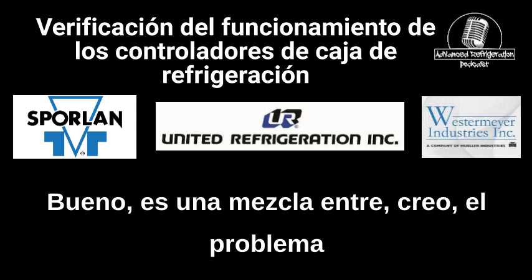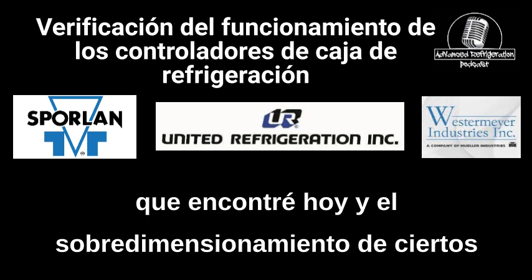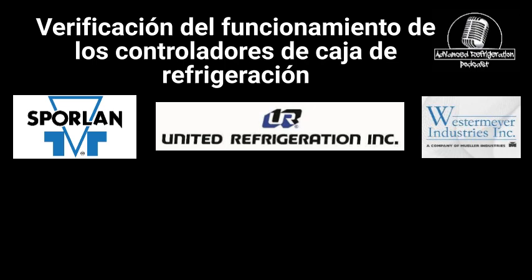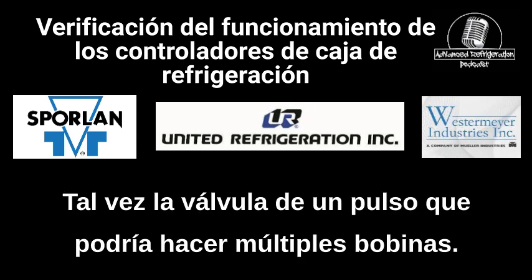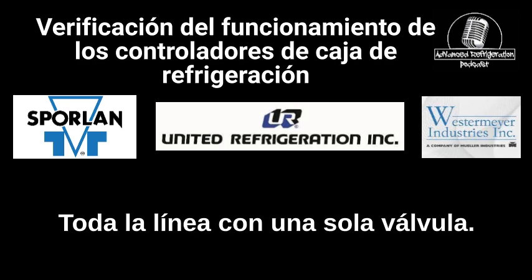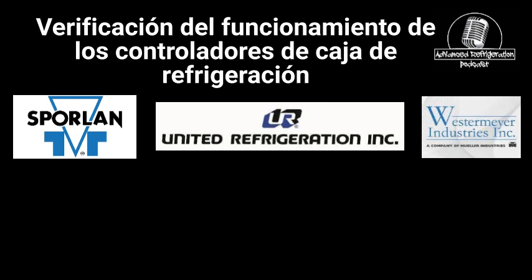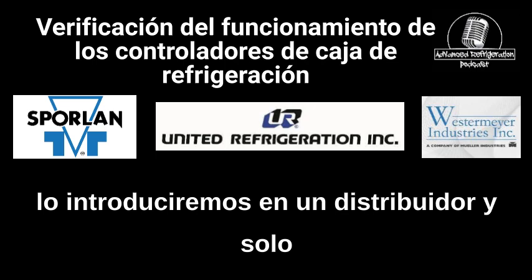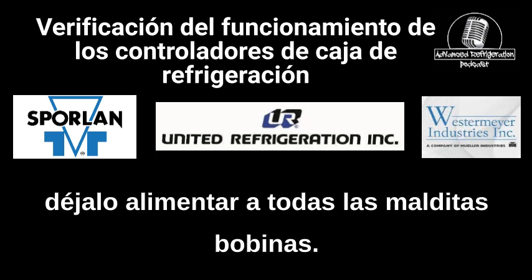Well, it's a mix between the issue that I found today and the oversizing of certain things, which just leads to really low suction. The pulse valves that are triple the size or double the size they need to be? Maybe. You mean the one pulse valve that could do multiple coils? Do the whole lineup with one valve. We'll rip out the other two pulse valves, and we'll just feed it into one distributor and just let it feed to all the coils.